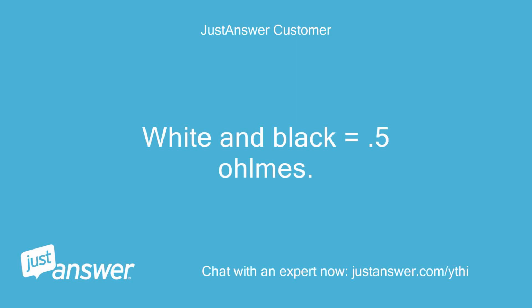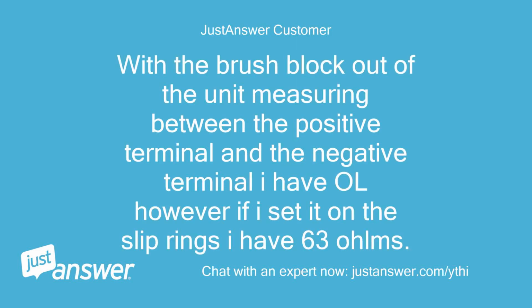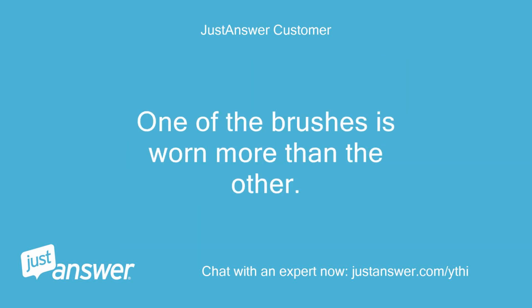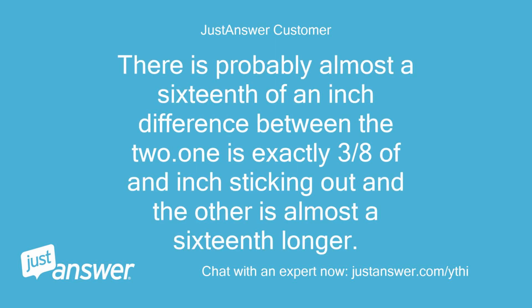White and black equals 0.5 ohms. Brown and red equals 0.7 ohms. With the brush block out of the unit, measuring between the positive terminal and the negative terminal, I have OL. However, if I set it on the slip rings, I have 63 ohms. One of the brushes is worn more than the other. There is probably almost a 1/16 of an inch difference between the two. One is exactly 3/8 of an inch sticking out and the other is almost a 1/16 longer.